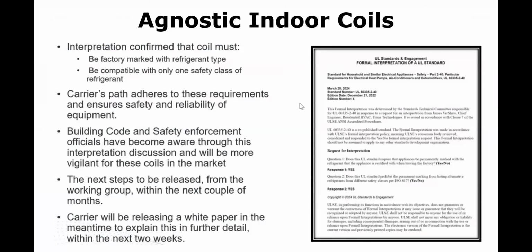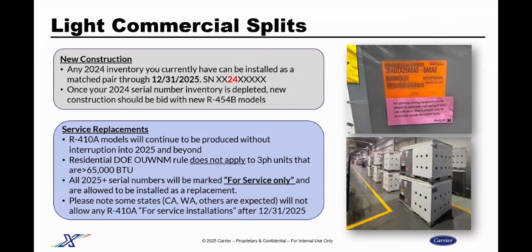There is, so the service only thing is the condensing unit only, not the air handler. But there is the ability to forever, with no end date, manufacture evaporator coils for furnaces. That's not part of any of the phase down for 410A stuff. So Carrier could keep making evaporator coils forever for 410A with a 410A TXV on them. There's no end date to that. But for condensing units, it's what I just described.